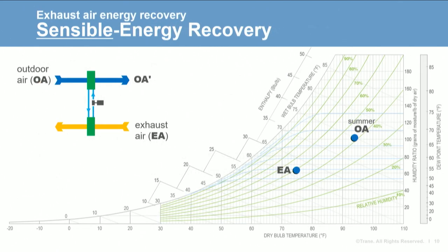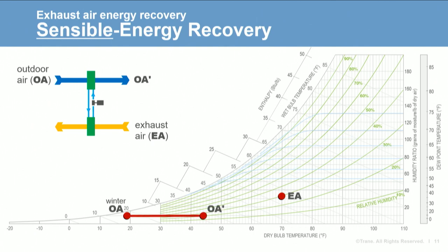The first chart depicts a sensible recovery device used for exhaust air energy recovery, showing operation at cooling design conditions in summer. When it's hot outside, sensible heat is transferred from the outdoor air to the cooler exhaust airstream, lowering the dry bulb temperature of the outdoor air and reducing the load on mechanical cooling equipment. At heating design conditions, the same device transfers sensible heat from the warmer exhaust air to the cold air entering, raising the dry bulb temperature and reducing the heating load.